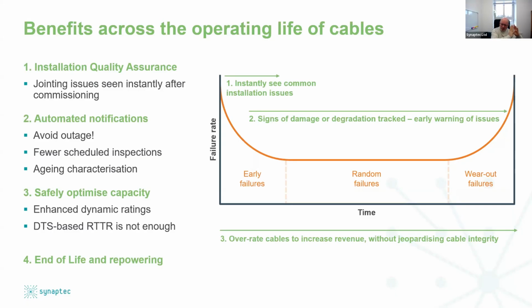because you will ideally always test the cable during commissioning to ensure there are no latent defects coming from bad handling or manufacturing errors. But even testing is not 100% perfect. And what would be ideal is that you run a test, and immediately afterwards, when you've energized the cable, then a green light is immediately working and noticing instantaneously if there's a problem. And we'll see that, for example, if we're looking at, I'm making up a number now, 100 cables, and 99 of them the same, and one of them shows a very high or elevated screen current ratio as compared to the phase current. That would mean that termination work wasn't done correctly, and you can still get your contractor, who is probably still on site, to come back and fix that problem and re-terminate.